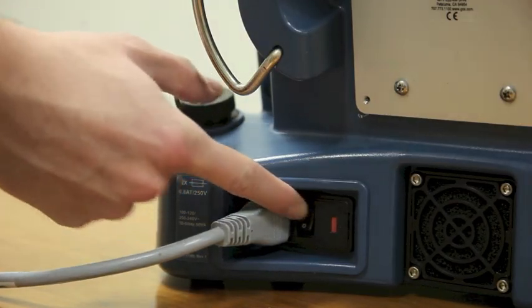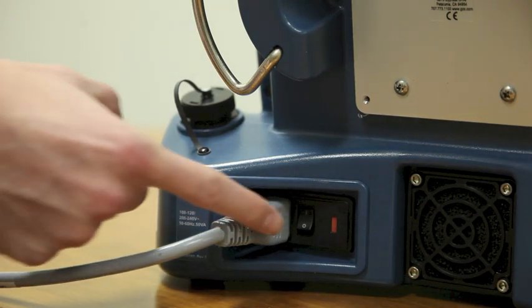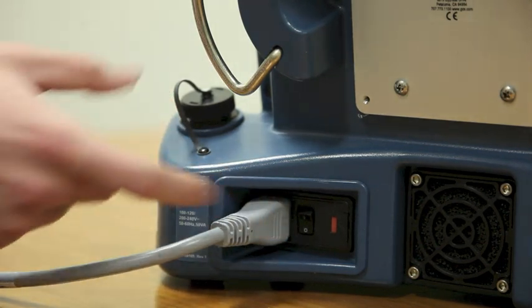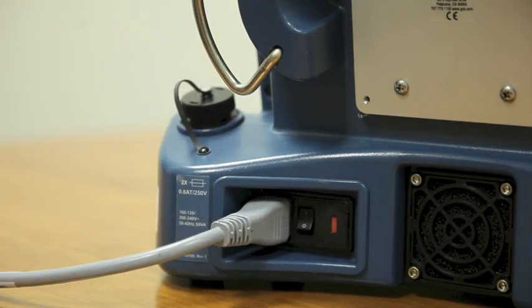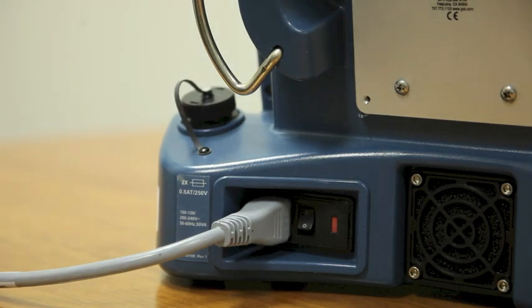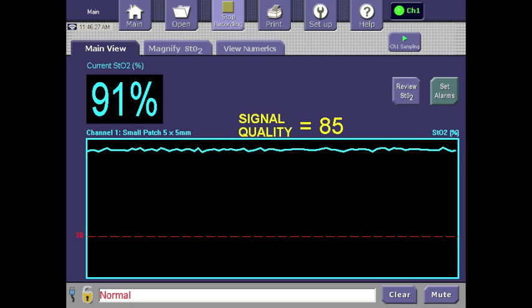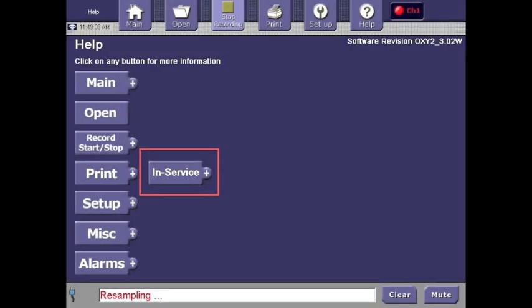As mentioned earlier, the rocker switch should always be in the up position towards the 1. It is recommended to keep the rocker switch up at all times, even when not in use. As mentioned previously, the battery has a 30-minute runtime and is meant for transport use only. If the battery does become fully depleted, it will take 3 hours to charge the battery back to full. In-service information can also be found under the Help button on the main screen.